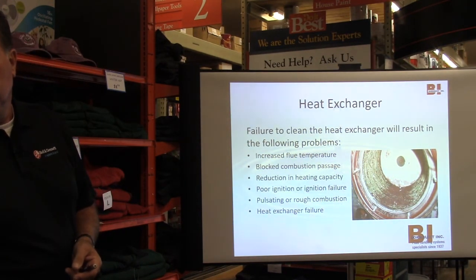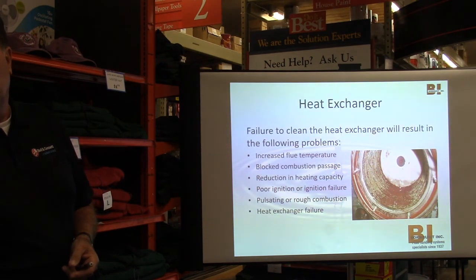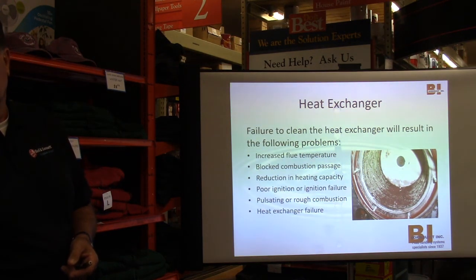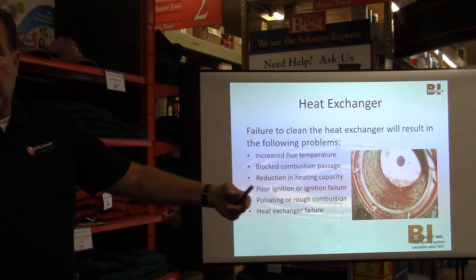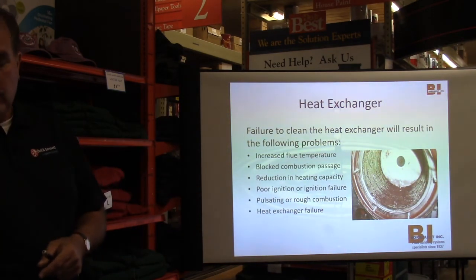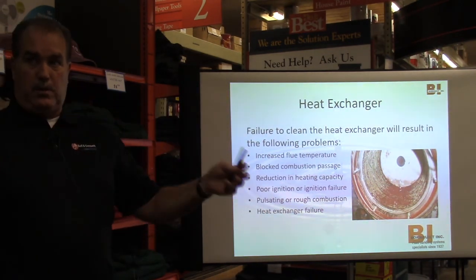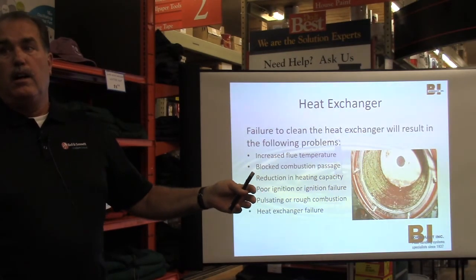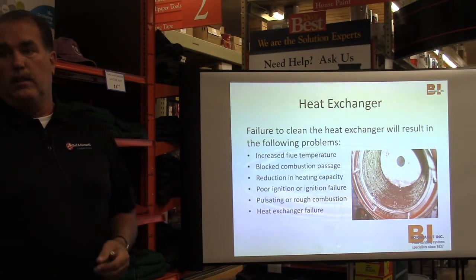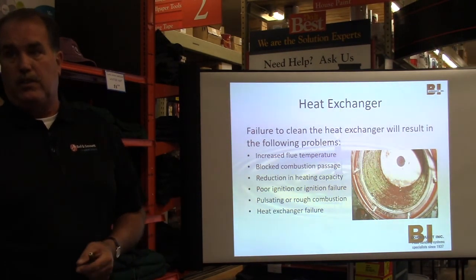Excuse me, where's the heat exchanger? In the boiler, the boiler's a heat exchanger. For hot water or for steam? Both. The heat exchanger is the big part of the boiler. Where is it? On the bottom? No, most of the boiler is your heat exchanger. Oh, the whole thing. That's just a term. The boiler itself is one big heat exchanger.